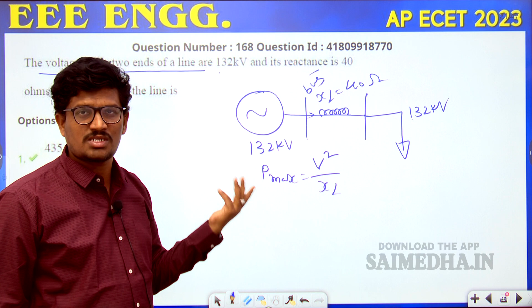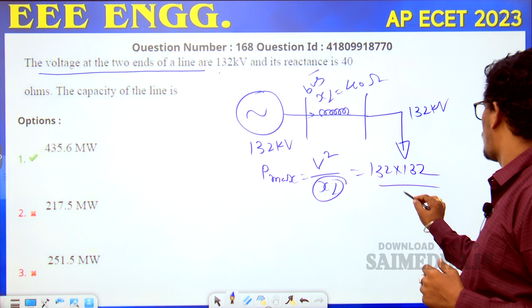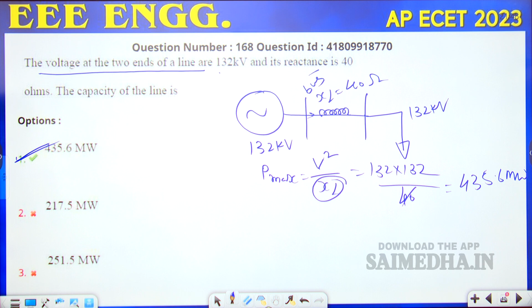What is the capacity of the line? The maximum power transfer in the line formula is V squared by XL. Since both ends' voltage should be the same, that's why it's V squared - 132 into 132, because both sides have the same voltage. So 132 into 132 divided by the reactance of the transmission line, which is 40. After simplification, this answer is 435.6 megawatts. So this is the formula, and answer 1 is the right answer: 435.6 megawatts. Let me go to the next question.